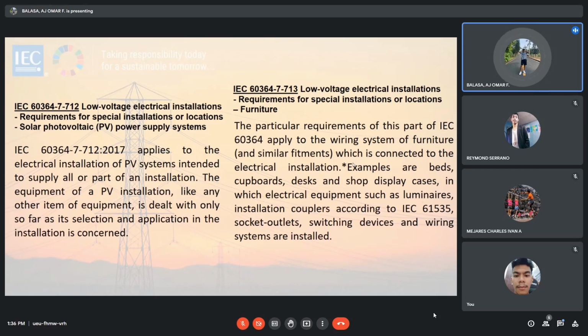Next. IEC 60364 Part 7, 713. Furniture. The particular requirements of this part apply to the wiring of furniture which is connected to the electrical installation. Examples are beds, cupboards, desks, and shop display cases in which electrical equipment such as luminaires, installation couplers according to IEC 61535, socket outlets, switching devices, and wiring systems are installed. The requirements of this part apply to all kinds of furniture, regardless of the connection to the electrical installation of the building, as long as the furniture together with its electrical installation is not the subject of another IEC publication.